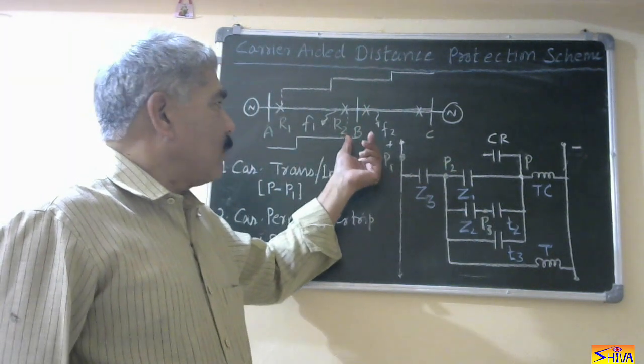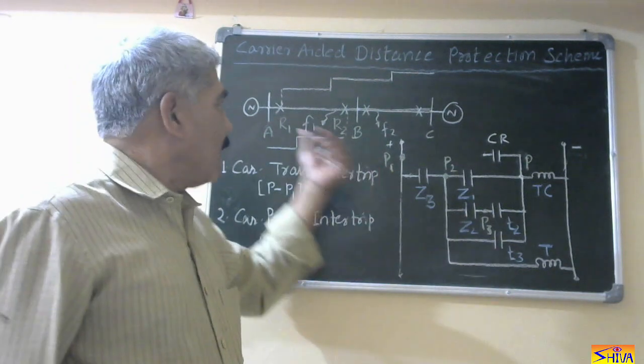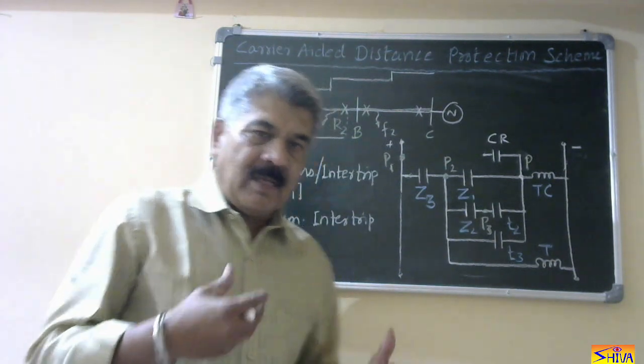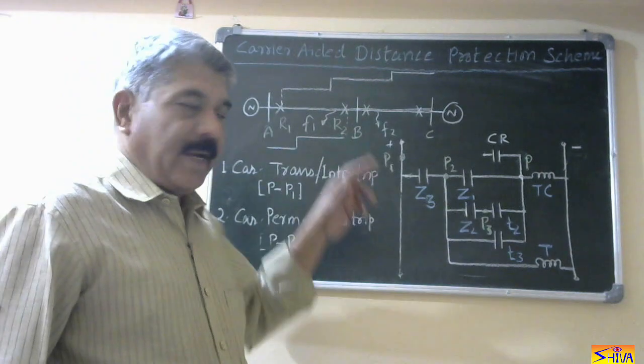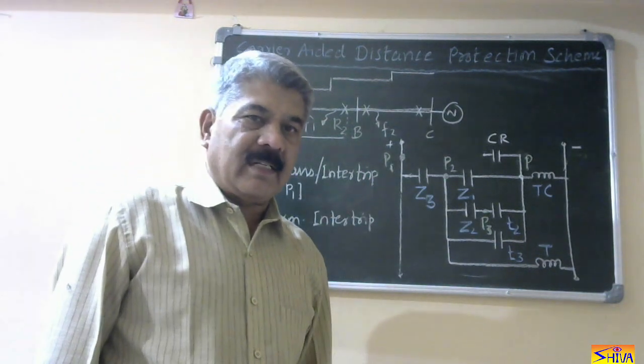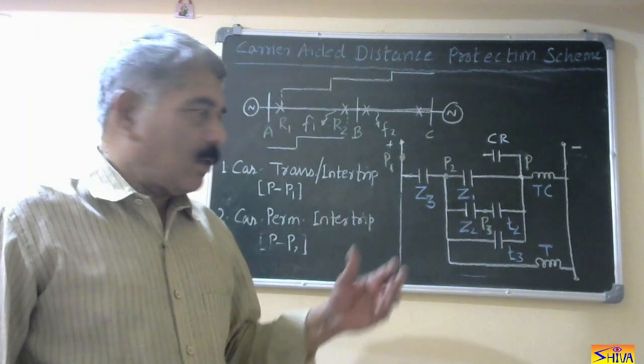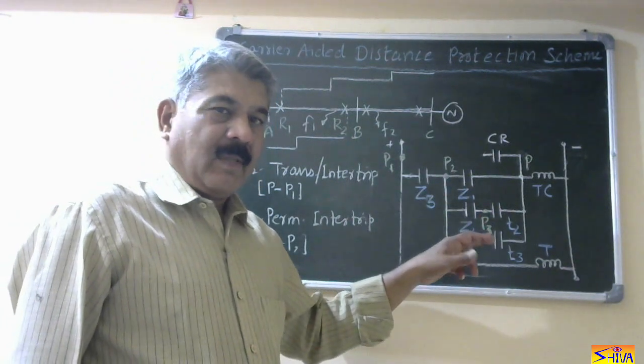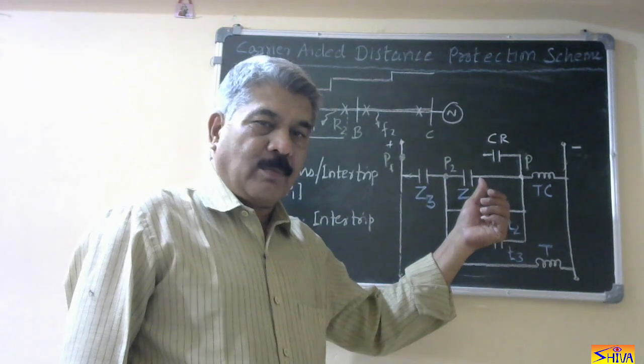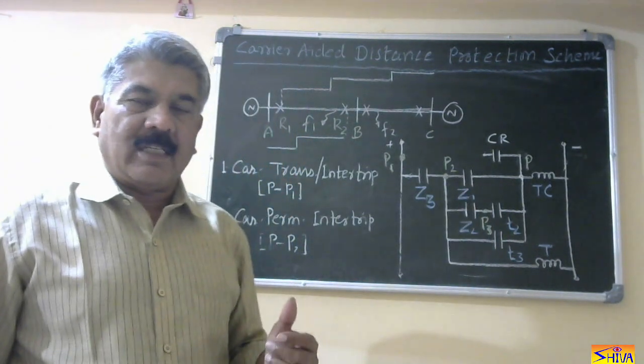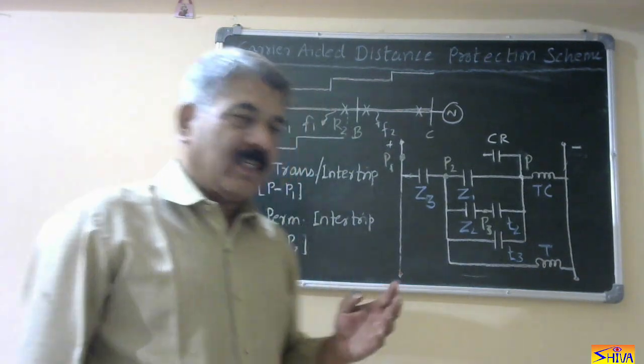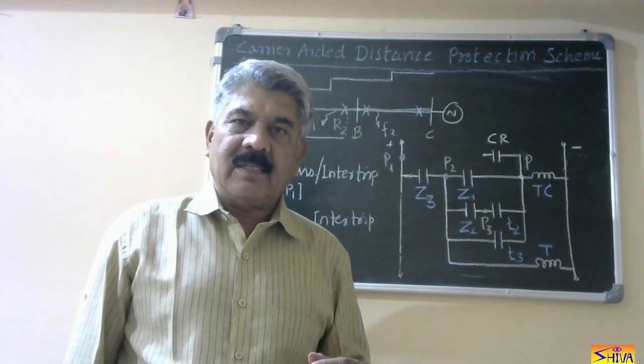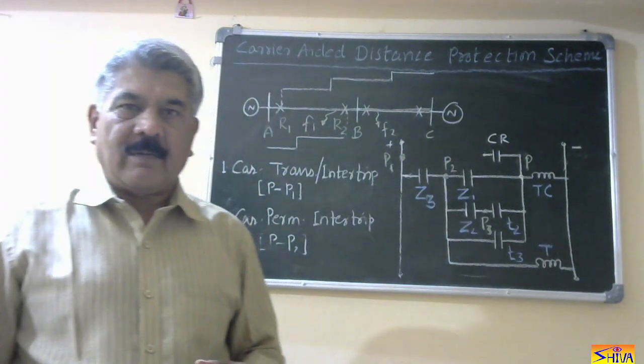It means R2 is operating in the first step for F1 and R1 is operating in the second step. Now, we have to extend the tripping zone of relay R1 up to end B. That is done by the carrier-aided distance protection scheme. According to the connection of the carrier receive relay in this contact diagram and whether this contact is open or closed, the carrier distance protection schemes are classified into four categories: first is carrier transfer or carrier intertrip scheme; second is carrier permissive intertrip scheme; third is carrier acceleration scheme; and fourth is carrier blocking scheme.